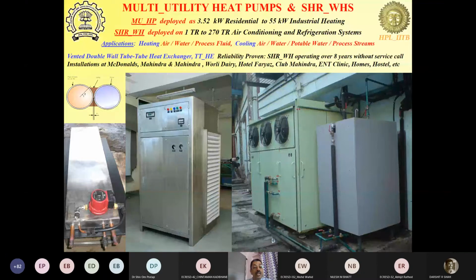So you have two tubes put up side by side. One of the tubes is carrying the hot fluid, and the other tube is carrying the cooler fluid, which needs to be heated. And then they are thermally bonded between the two tubes. So in case any leakage is there from any of the fluids, it will go into the atmosphere and not go into the second fluid. So that is the primary advantage of this. And because of this advantage, you can directly heat or cool the process fluid or potable water, which otherwise may be a concern, because in case the refrigerant leaks and mixes with the water which you are heating up, that water may not qualify as potable water. It may not be consumed or things like that.